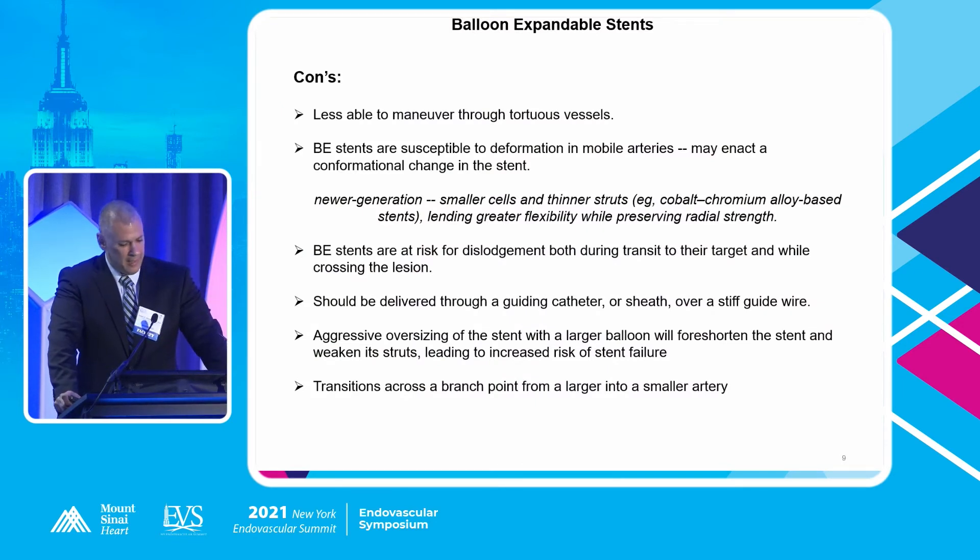Cons of balloon-expandable stents: they're less able to maneuver through tortuous vessels and tend to be bulkier in terms of their delivery system. You want to deliver them with a sheath because they can be displaced while traversing a tight lesion. These stents are susceptible to deformation in arteries that torque and twist, causing permanent conformational change — though newer cobalt-chromium constructions are more flexible than older stainless steel designs. They're also at risk for dislodgement in transit and should be delivered through a guiding catheter. Aggressive oversizing will foreshorten the stent, distort the struts so they don't appose the vessel wall well, and lead to stent failure and premature restenosis.